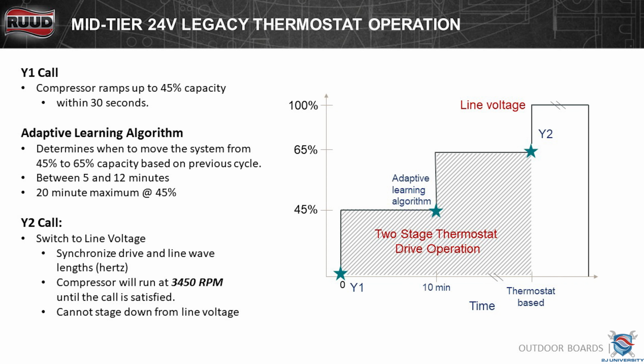On a 24 volt application, so if you're legacy wired, you've turned it into a 3-stage outdoor unit. Y1 call, it's going to go to 45%. It's going to run at 45% for roughly 5 to 12 minutes, but no longer than 20 minutes. Okay? Then it's going to stage up to 65%. It'll run at 65% until your Y2 comes in. Once Y2 comes in, then you get the line voltage and it goes to 100%.